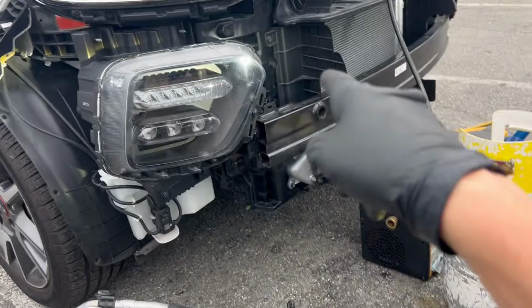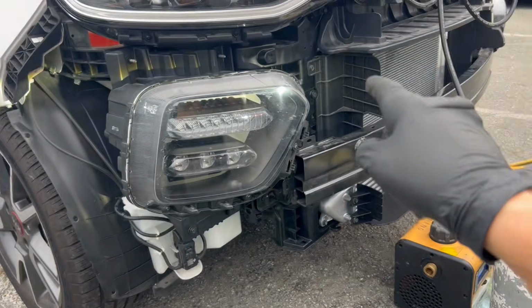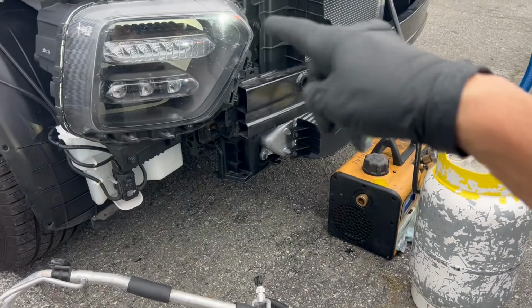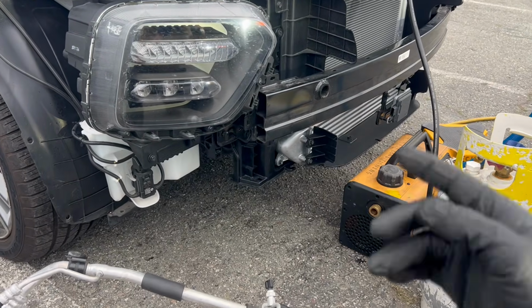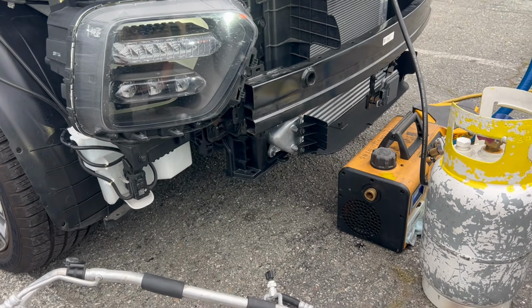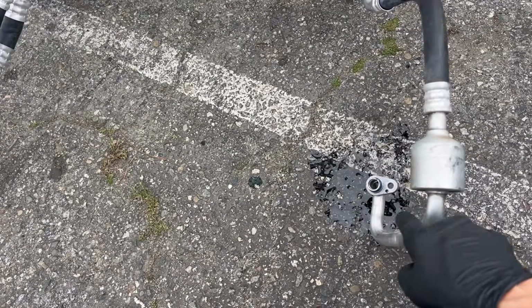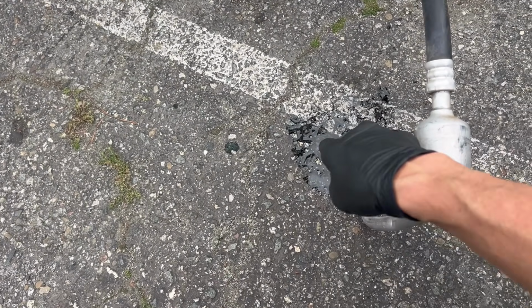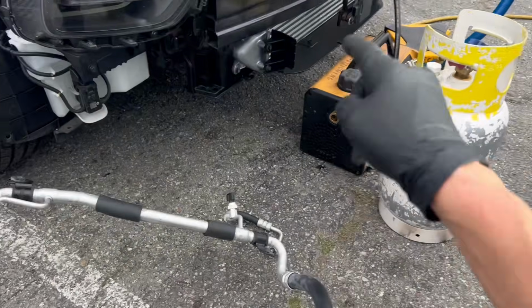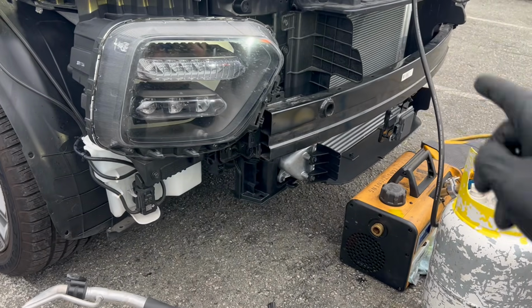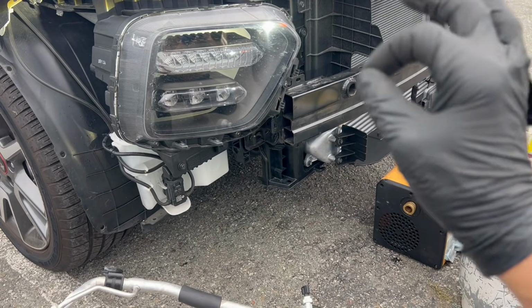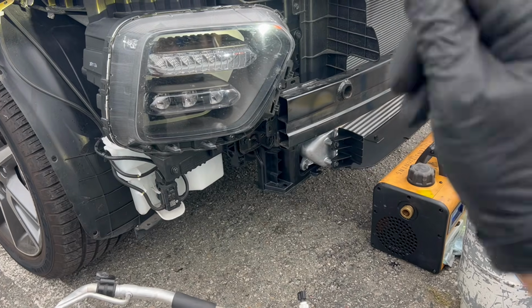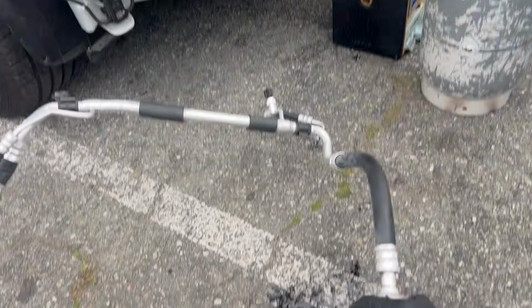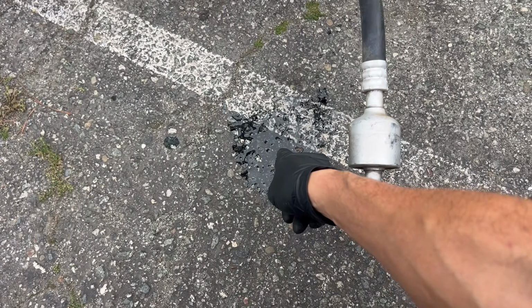Now, I recovered last week. I recovered the refrigerant. They didn't get the parts and everything done until a week later. They had the system open to the atmosphere. This has been sitting in that box for several days with oil trapped, with refrigerant trapped inside the oil. When I used the recovery machine to vacuum out this oil, I had it down to 800 microns. 800 microns of vacuum. Wouldn't you think all the refrigerant came out of the oil?